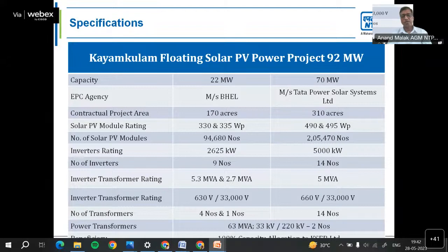The inverter transformer ratings are 630 by 33 kV, and in case of 70 megawatt, it is 660 volts by 33 kV. The number of transformers is 4 and 1 in 22 megawatt, and around 14 in 70 megawatt, 14 into 5 megawatt each. All the power generated by this 92 megawatt is fed to two power transformers of 63 MVA, 33 kV by 220 kV.